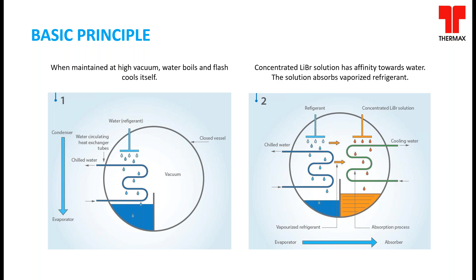At the end of the absorption process, after absorbing the refrigerant vapor generated in the evaporator, the concentrated solution of lithium bromide becomes dilute. It gets collected at the bottom of the absorber. Now the next step is to regenerate the concentrated solution and regenerate the refrigerant. To continue this process in a cyclic manner, we go to step number 3, which is to regenerate the refrigerant. We take this dilute solution from the absorber and pump it into the next section called the generator. In the generator, we use the heat source that we discussed in the beginning. A waste heat source or a live heat source is used to boil the lithium bromide solution, and we separate the refrigerant vapor out of it. Once the refrigerant vapor gets separated after boiling out, what gets left behind is the concentrated lithium bromide solution, which can be taken back into the absorber section for further cyclic activity.